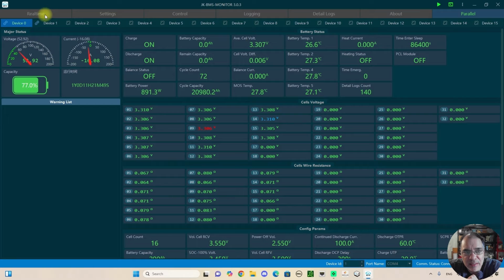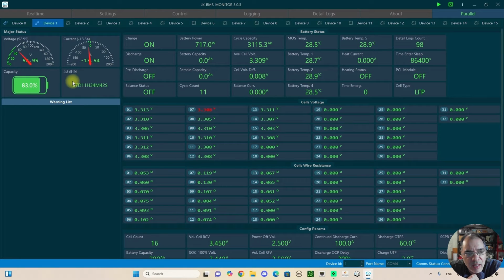You can see that all the functions up here are disabled - that's because we're in parallel mode. When you're in parallel mode, you're able to see all your devices in parallel. So device 0 is our master, and we can see the voltage at 52.92, current 16.46 amps going out, and we're at 77% state of charge. Then we can flip over to device 1, which is slave 1, and we can see that we have 83% state of charge on this battery.